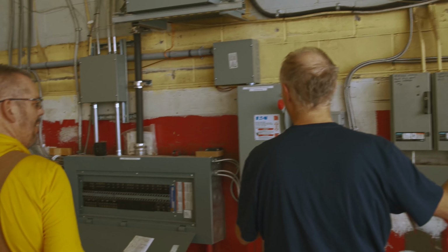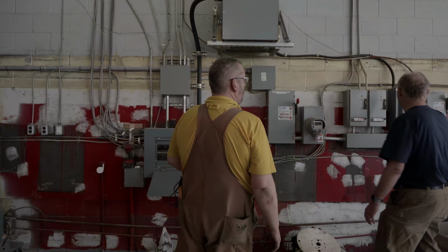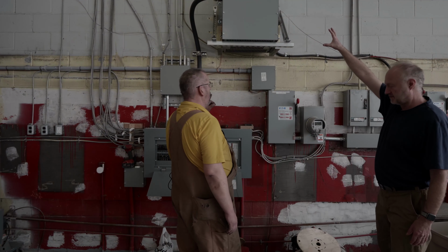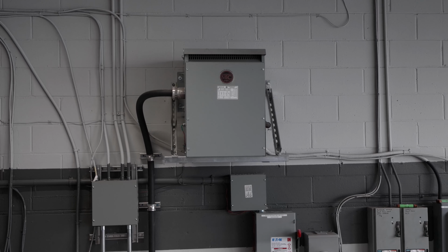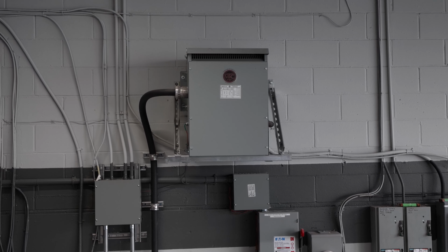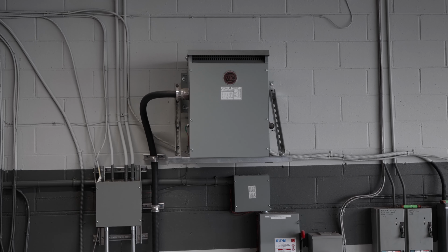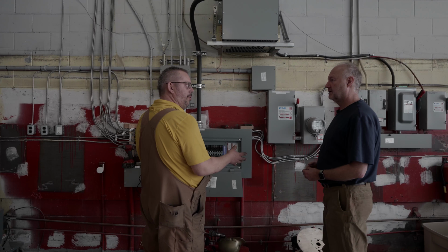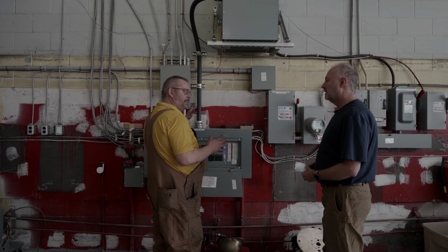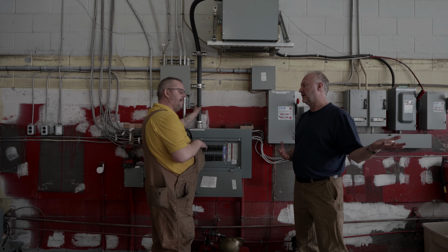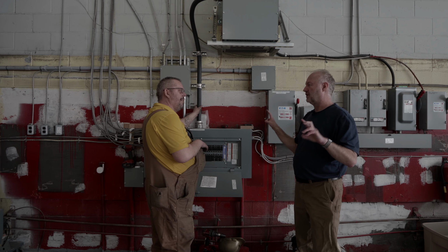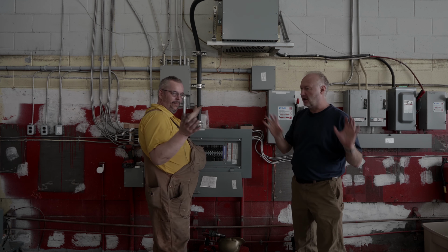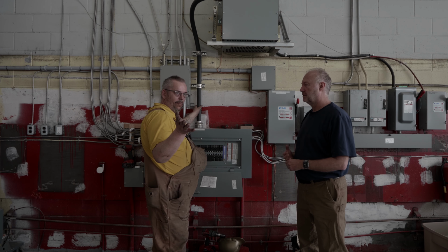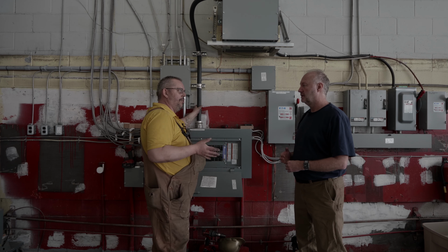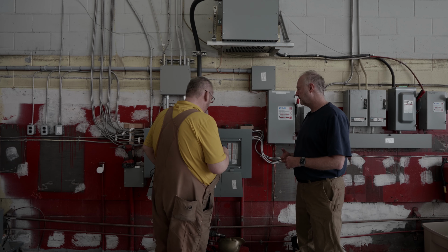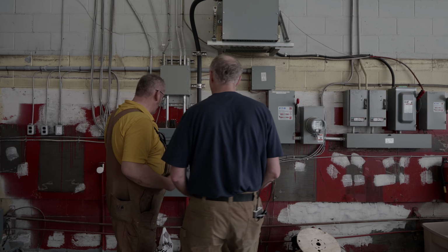So the rest of the power for the shop comes through this disconnect up here into this big transformer. Yes. And that is converting the three-phase 600 volts to three-phase 208. Because in a commercial situation, instead of 240, you're going to have 208 volts. Yeah. Most equipment will run without issue, so that's what we've been finding. So all the equipment we have here is home use, like 240 volt or 230, but it all runs just fine on 208. Technically, it was all designed to be used commercially. So while it's small, it works well on 208.